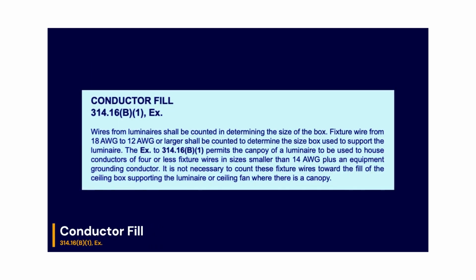Conductor fill. 314.16(B)(1) Exception. Wires from luminaires shall be counted in determining the size of the box. Fixture wire from number 18 AWG to number 12 AWG or larger shall be counted to determine the size box used to support the luminaire.